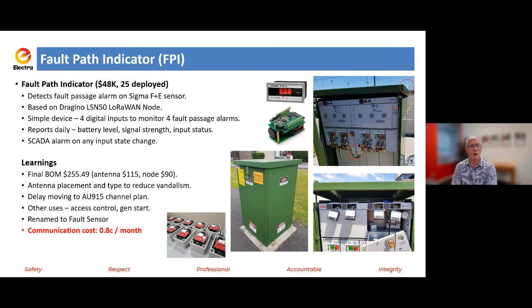We put it into a Sigma F+E fault passage indicator, and whereas that would normally just trigger a strobe, it now also triggers our FPI indicator, which sends us an alert. That alert comes up in SCADA and allows us to act on it. The final BOM for that was about $250, so not expensive.